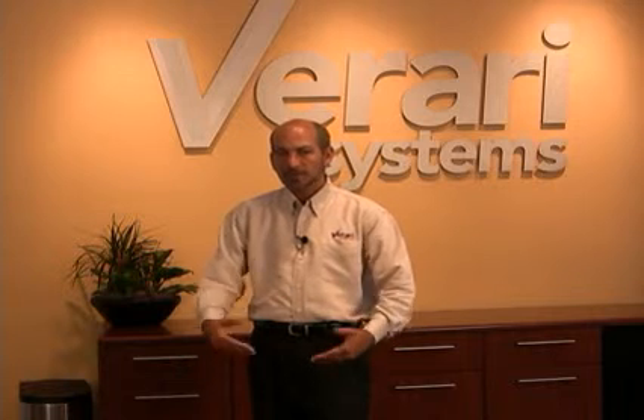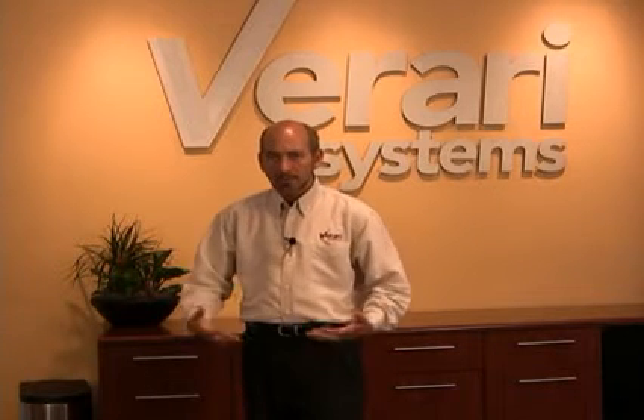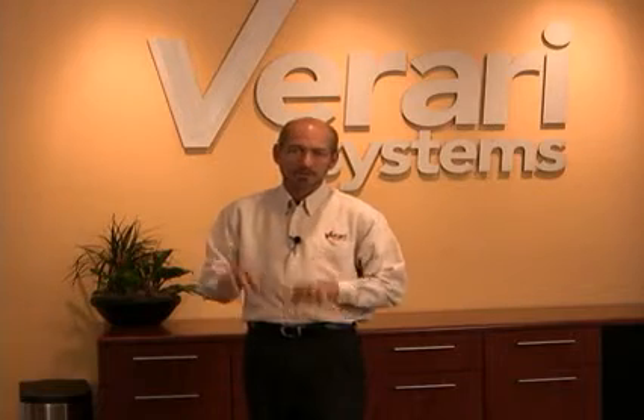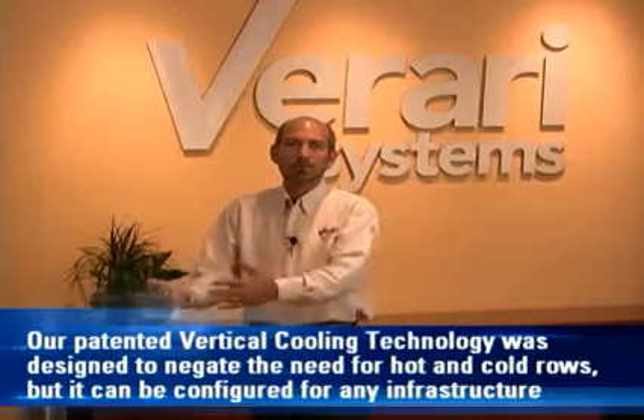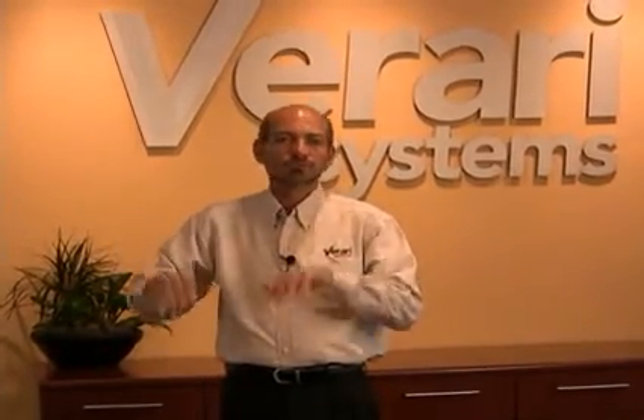At the first level, prior to entering the cabinet or prior to entering the nodes, we have a row of fans. Those fans actively draw either directly from underneath if it's a raised floor environment, or from the front or the back, or both sides, depending upon if you're in a hot and cold row environment or a cold row environment. We're capable of taking in air from any aspect that the room really mandates. The air is then actively pushed up through the nodes. We have anywhere from 2 to 4 rows of blades.